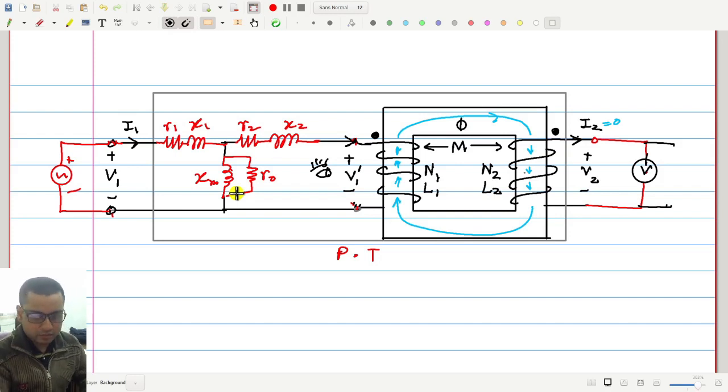Under that situation we want to measure the error in the measured voltage and the phase angle error. So this is the voltmeter in the secondary, and the quantity that we are actually measuring is this voltage. When we multiply the voltmeter reading with the turns ratio, then we will get this voltage, and this is the input voltage that we want to measure.